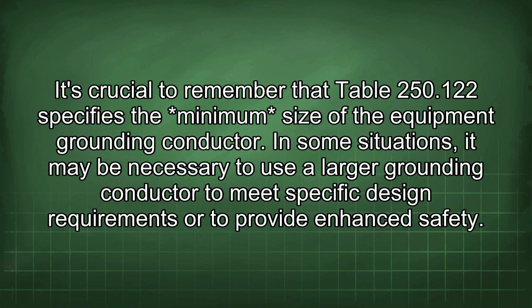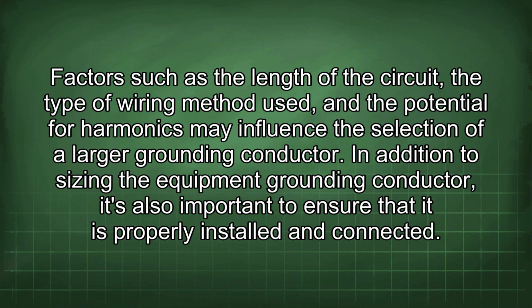It's crucial to remember that Table 250.122 specifies the minimum size of the equipment grounding conductor. In some situations, it may be necessary to use a larger grounding conductor to meet specific design requirements or to provide enhanced safety. Factors such as the length of the circuit, the type of wiring method used, and the potential for harmonics may influence the selection of a larger grounding conductor.